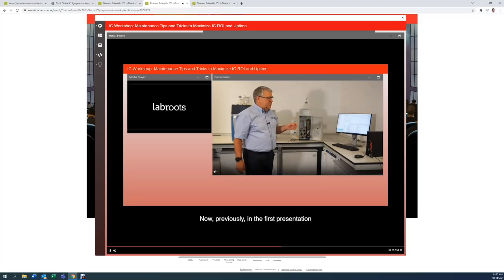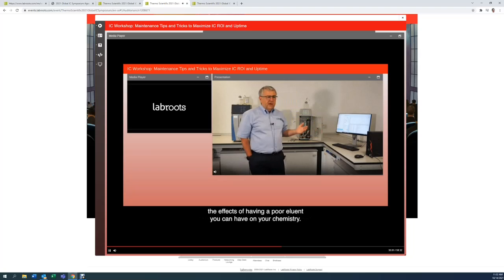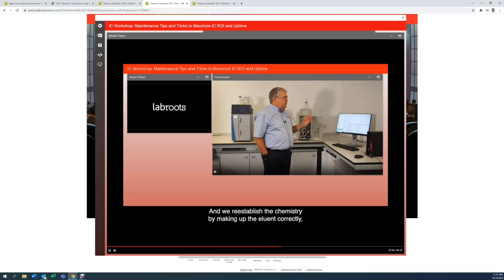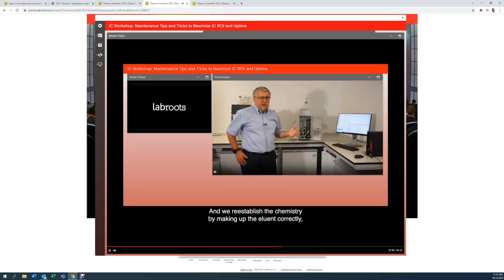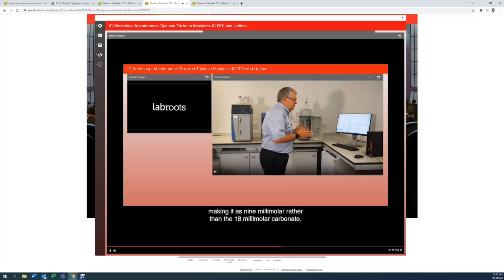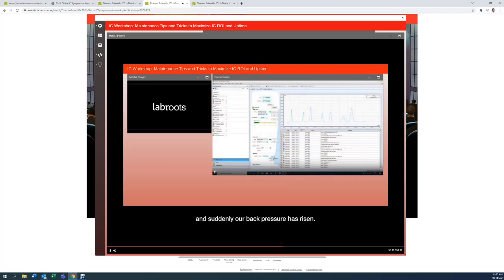Previously, in the first presentation, we were talking about eluent quality and the effects a poor eluent can have on your chemistry. We re-established the chemistry by making up the eluent correctly, as 9 millimolar rather than 18 millimolar carbonate. Now we've put the system back on again, and suddenly our back pressure has risen. It was running previously at 2,000 psi. Today, as you can see, it's running at around 2,500 psi, which means we've gained 500 psi.